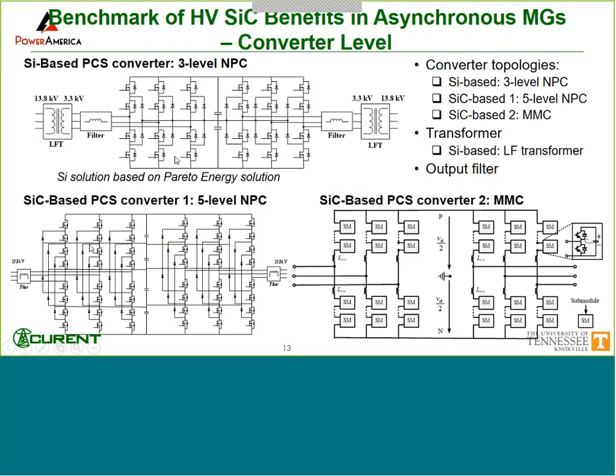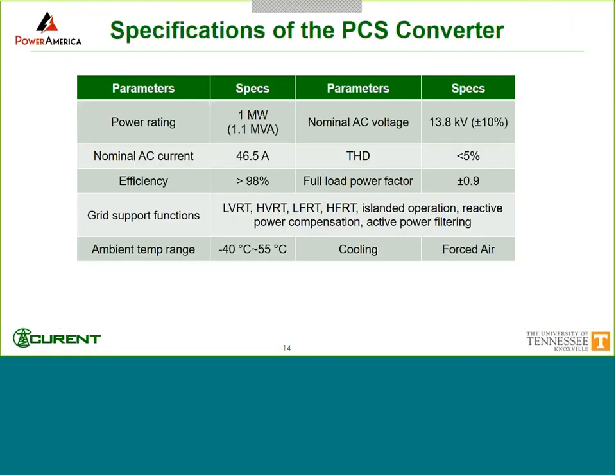We have basically done three comparisons. The first one is a baseline with silicon. That is a similar picture to what I just showed, with 3.3 kV AC voltage through a transformer to 13.8 kV. Then two silicon carbide based topologies: one is a 5-level NPC, the other is an MMC. In both cases, we have done exactly the same design for the same spec. And here is the spec we have used. Basically, it's a 1 megawatt design. This shows the different voltages and currents, the THDs, efficiency, and also the different grid support functions needed, the ambient temperature, and the cooling condition.